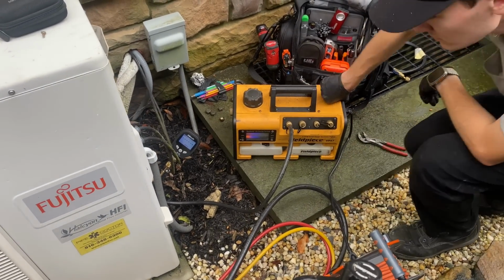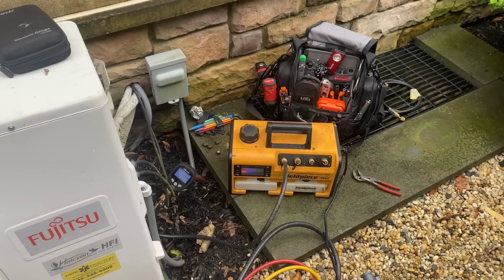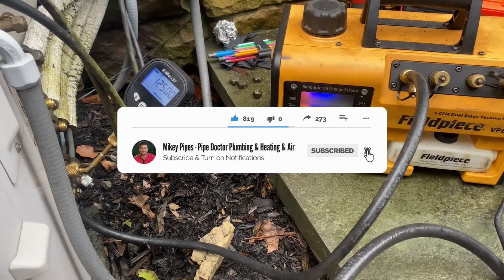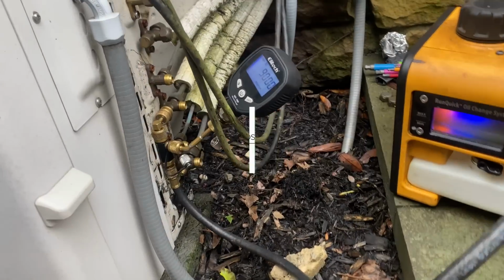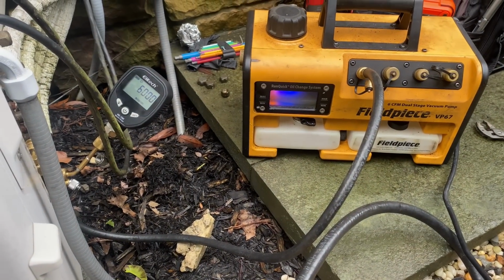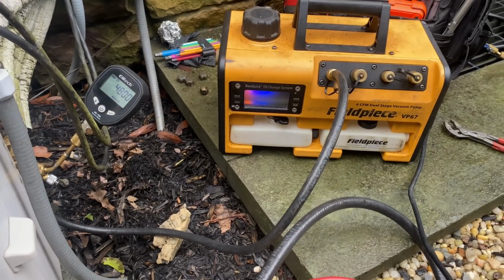All right, the unit's connected. Electric is done. Passed the pressure test. Now we're gonna vacuum it down. Daniel's using the Elitech refrigeration vacuum gauge or micron gauge. Nothing fancy here. Just looks like he pulled the core out. Standard hose. 6,000 microns and dropping. Not too shabby.